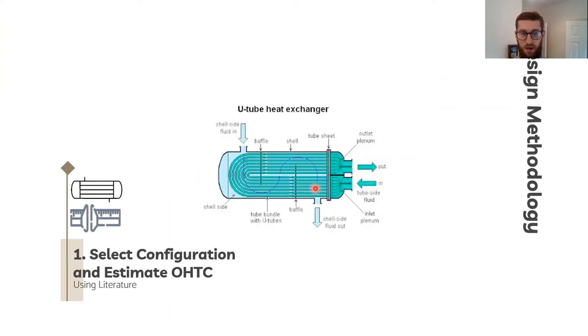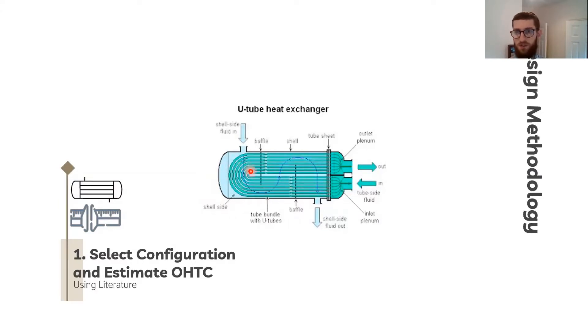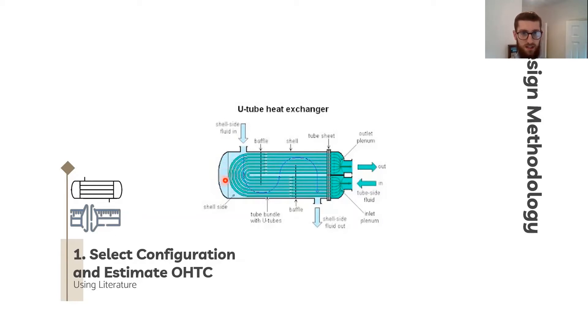There is a large temperature difference between the gas and the cooling water, and this configuration is the cheapest way to allow thermal expansion of the tubes without damaging the heat exchanger that can expand into this space here.